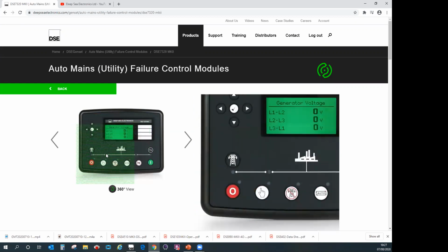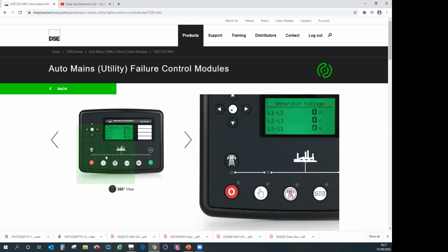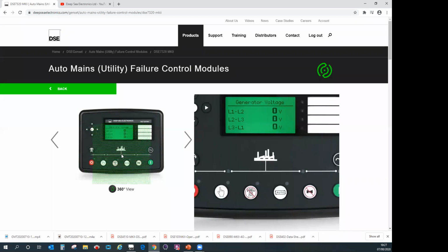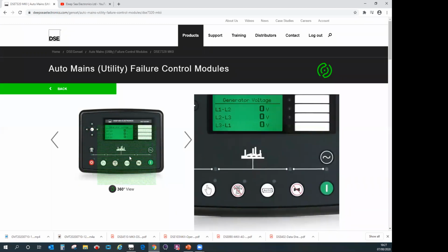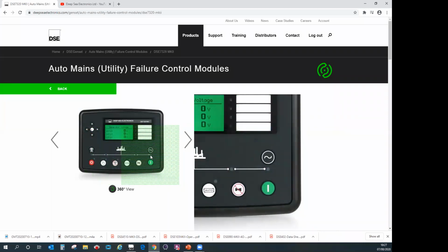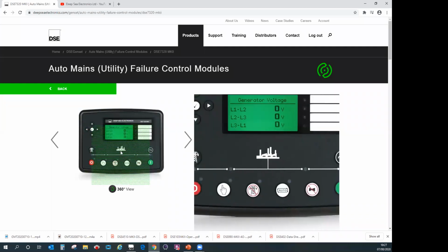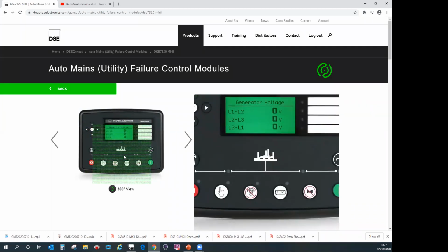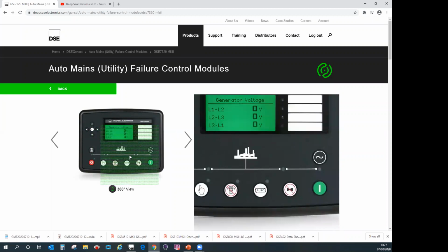Should the mains fail, then the mains breaker will open and the generator will be instructed to start. The generator will then start and it will become available, so this LED will light here, and then this breaker will close, and it will provide power to the site. Okay. So this has a few more features compared to the 10. Essentially, it's monitoring the mains, whereas a 10 is not monitoring the mains. It's just a standalone Genset controller. So obviously there's a small difference in price, but in terms of actual control of the generator, it's the same thing.